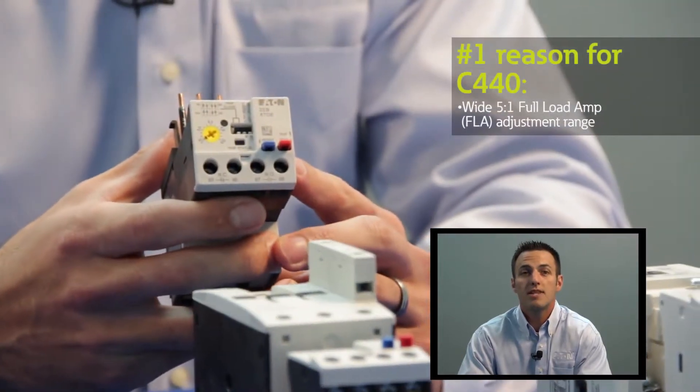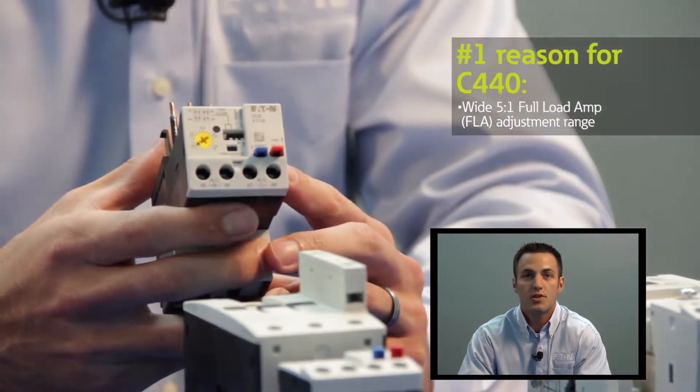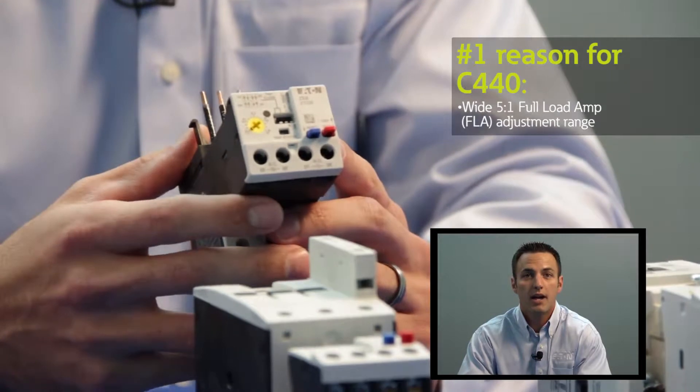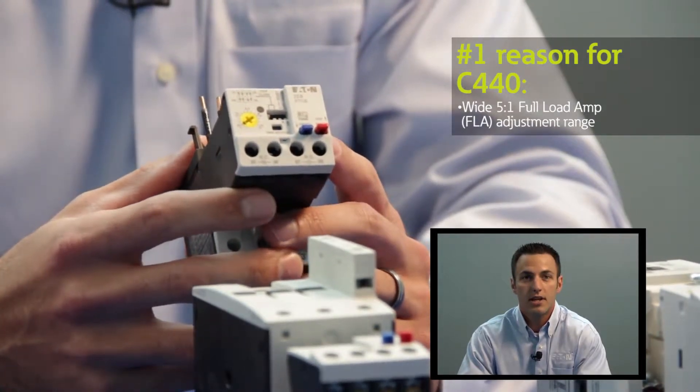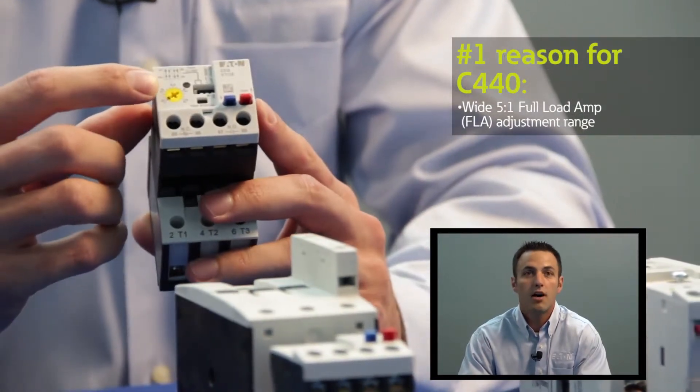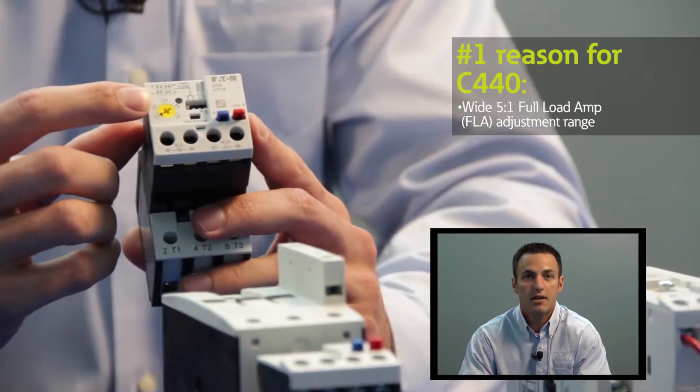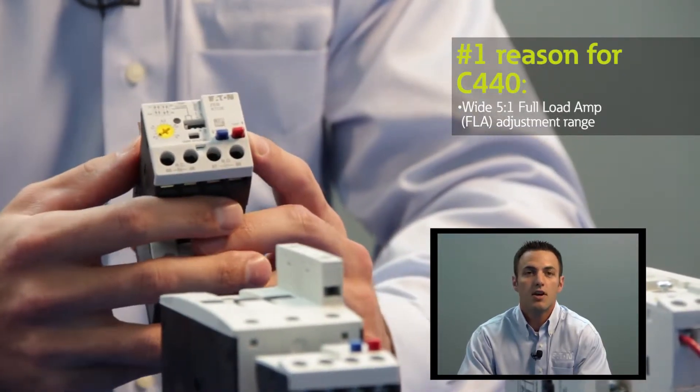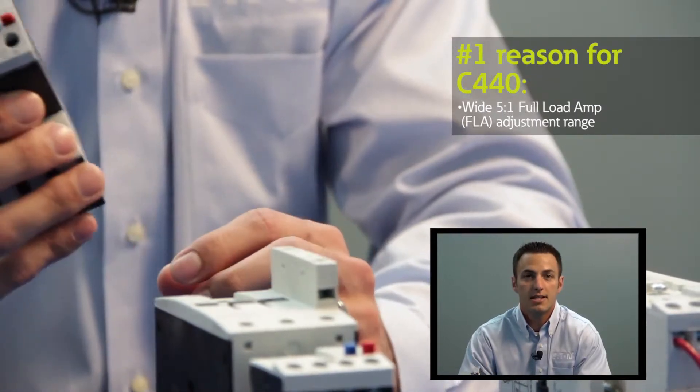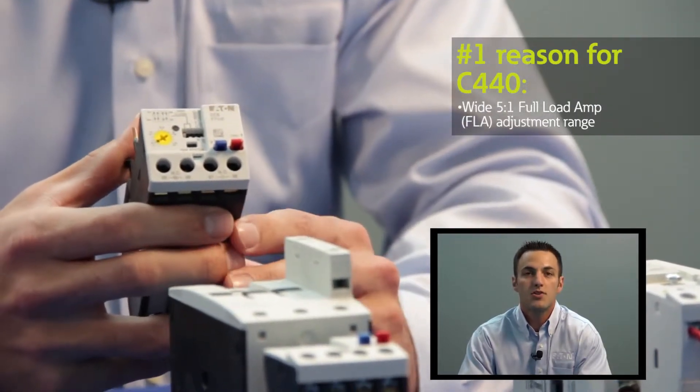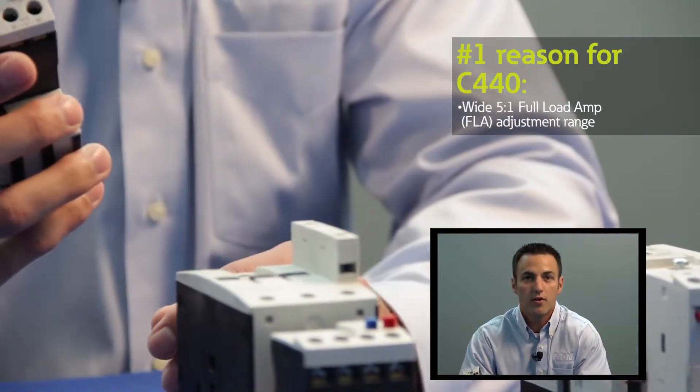Unlike traditional bi-metallic overloads that require the user to purchase separate heater packs matched to the exact application, the C440 offers a large 5 to 1 full load amp adjustment setting such as 4 to 20 amps or 20 to 100 amps in a single device. This allows you to cover a much larger set of applications with a single overload.